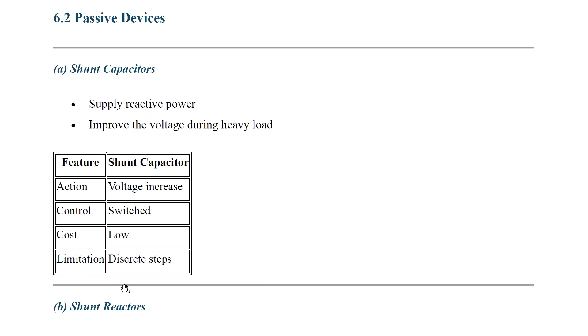Coming to the shunt reactors. Shunt reactors means inductance. So it absorbs the reactive power and is also used at light load, as the Ferranti effect will also be induced in these shunt reactors. If you take voltage reduction, the main role of the shunt reactors is voltage reduction.